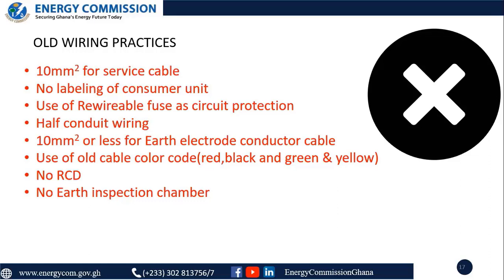That's for single phases. Then the old wiring practice, they weren't using RCD. Electricians weren't using RCDs, which now you and I can confirm is a must-have device to be installed in an electrical installation or wiring. And then they weren't creating an inspection chamber. It was very difficult to get access to the earth rod once you've buried it, because they cover it entirely with sand. So how would you be able to confirm that the electrician has even buried a rod in the ground and has connected the cable to the rod?